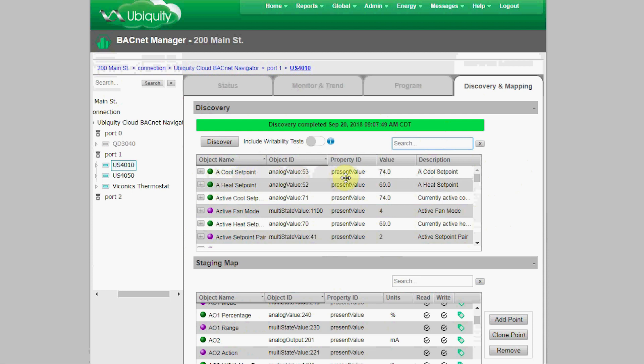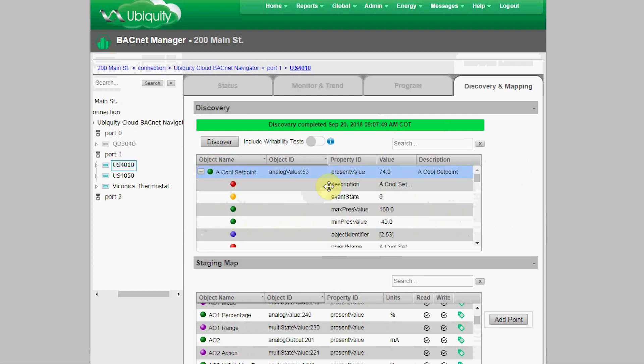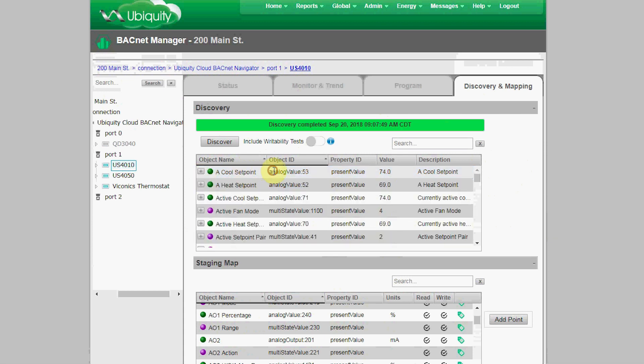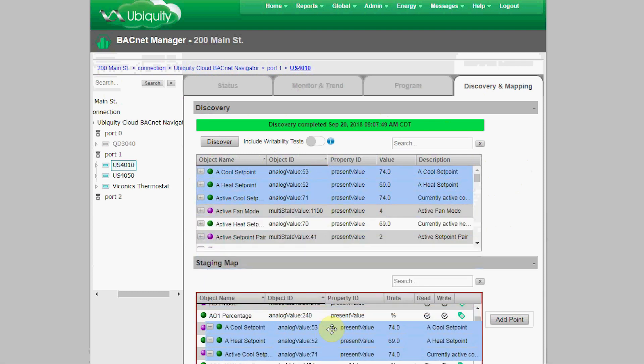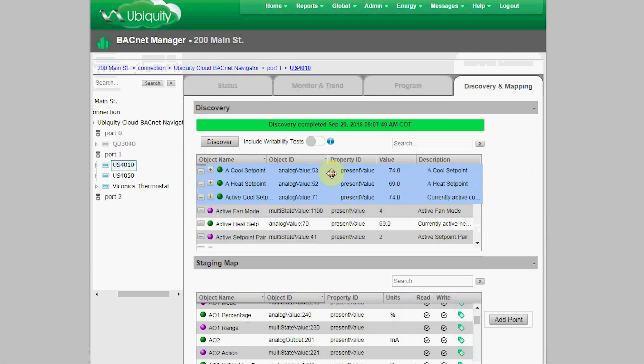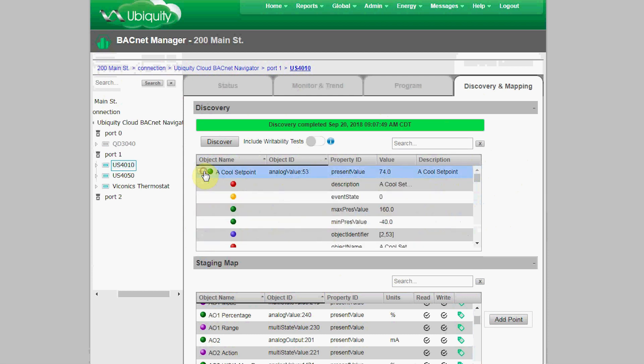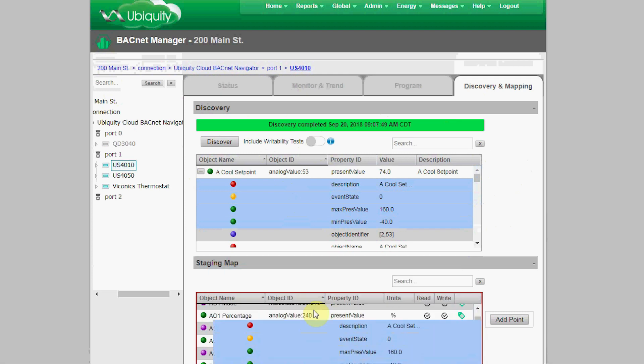The BACnet Manager presents each present value for each object. Clicking on the plus button will show the associated properties to that present value object, including color-coded data type which has a scroll-over tooltip. In this case, a red point is a character string, a yellow point is an enumerated value, and so on. You can highlight the present value objects then drag and drop them into the Staging Map.